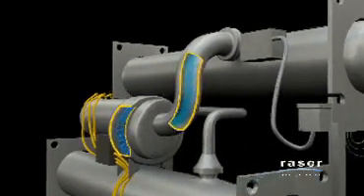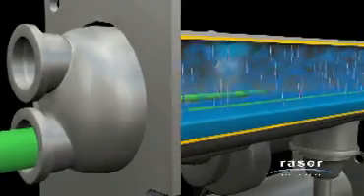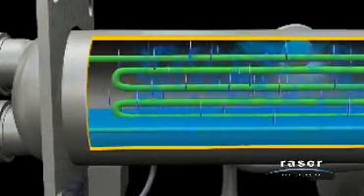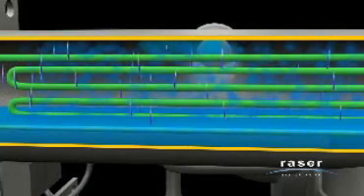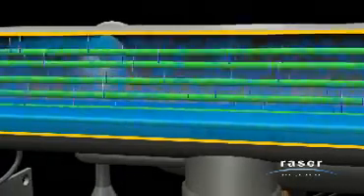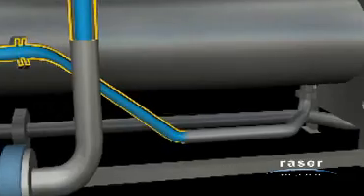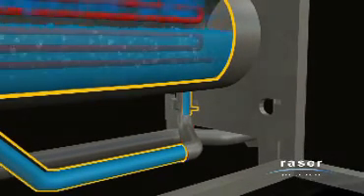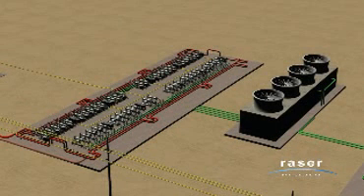After leaving the turbine, the steam moves upward into the condenser tank. Here, cooling water enters the condenser from the cooling towers and circulates through coils in the condenser tank, cooling the steam and allowing it to condense back into a fluid collecting at the bottom of the tank. The cooling water enters the tank at about 67 degrees, but after cooling down the working fluid, it leaves the tank at about 87 degrees. The working fluid now flows down the tank outlet to the pump, where it is repressurized and injected back into the heat exchange tank to repeat the process.